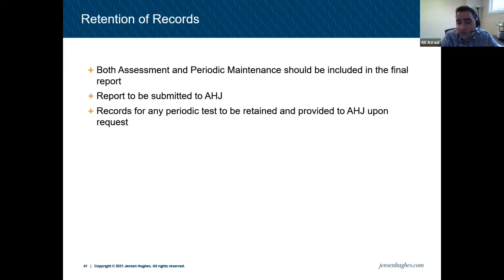So retention of records, there's another requirement in the fire code for this. Both when you're doing an assessment and periodic maintenance, there should be a final report with the assessment, the test result of your initial test if you did that, and an empty form for the owner to use moving forward for the test and maintenance procedure, attached to that report. It needs to be submitted to AHJ for review and approval, and you have to record it and do the periodic test. It needs to be provided to the AHJ upon request. So typical, as other records that you need to keep for the fire life safety systems.